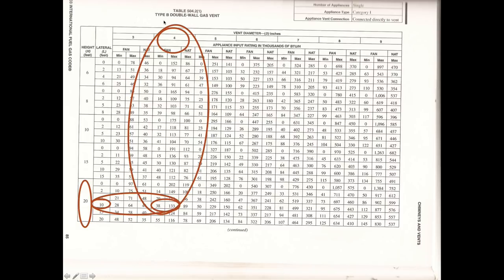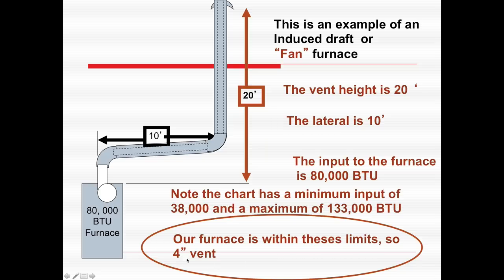One thing to go through here — these charts are confusing. Notice right here we have Type B double wall gas vent. Over here: number of appliances — one single appliance, category one, connected directly to vent. If you're looking at the different charts, you've got to be sure you've got the right one. There will be one for single wall vents, ones for masonry chimneys, ones for multiple furnaces, and so on. Getting to the right chart is probably the hardest part. So we end up with a four-inch vent on this appliance.